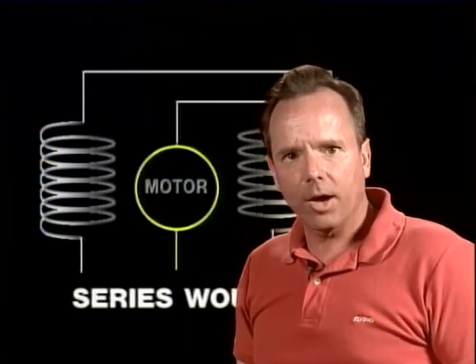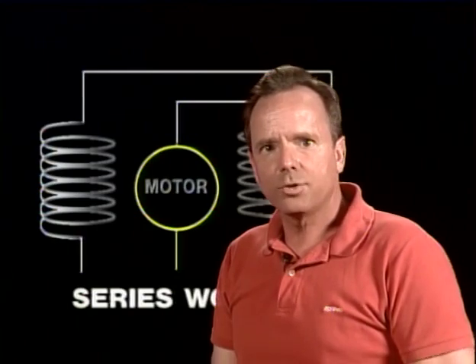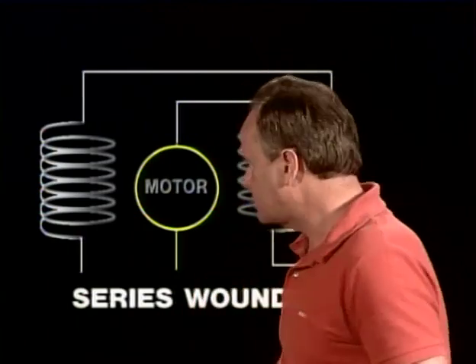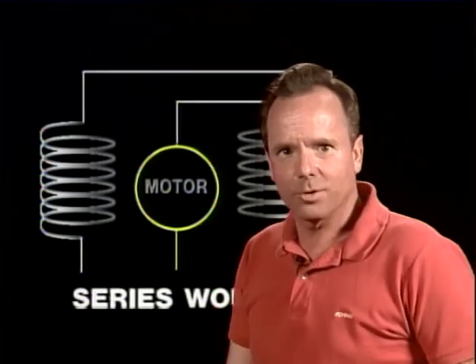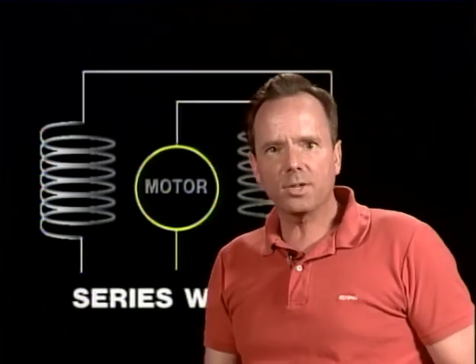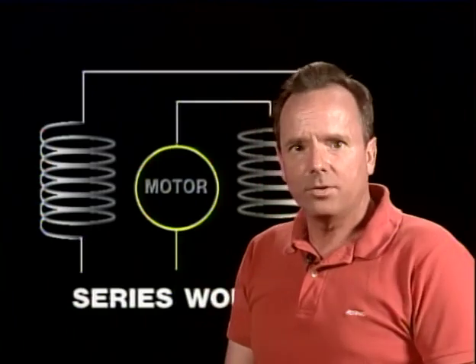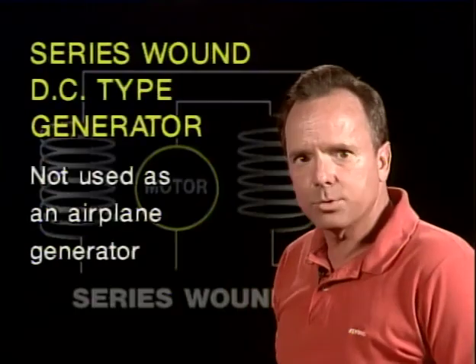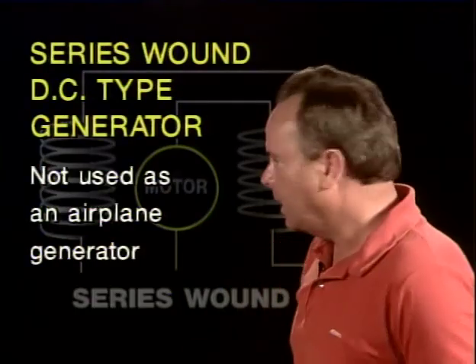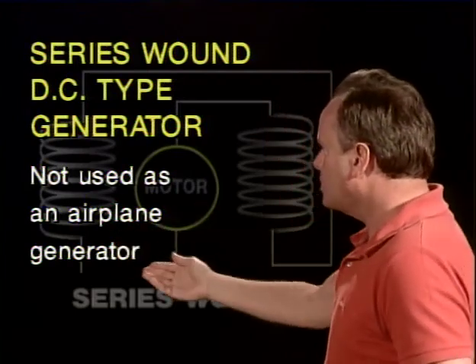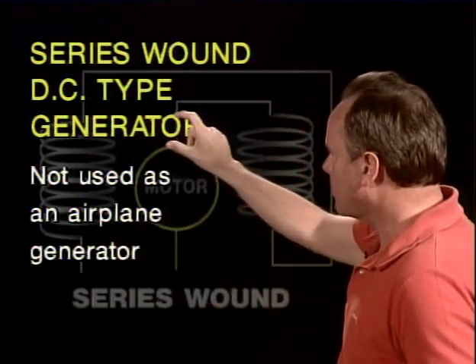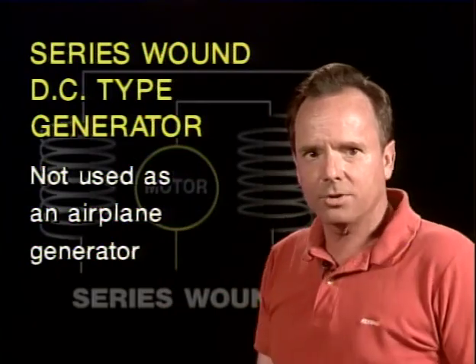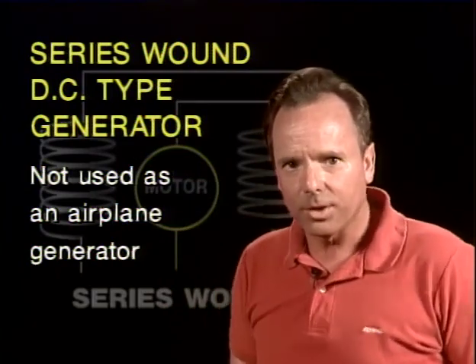Now let's take a look at the characteristics of a series wound generator. First of all, it could either be a motor or a generator, by the way, that could be series wound, because remember, motors and generators are almost the same thing. So first of all, let's take a look at a thing you need to know about a DC type generator, series wound. One of the things you need to know is it's not used as an airplane generator. Series wound DC type generators are not used as airplane generators. That's something you need to know for the test.